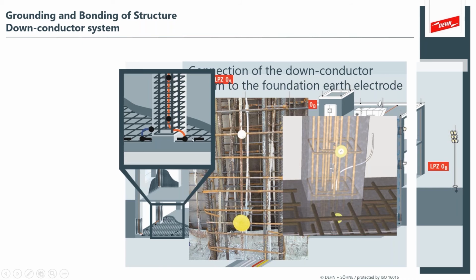So the point of grounding and bonding always comes together hand in hand. And when you have equipment, you might have an electrical control cabinet that might be sitting near this column, and when the structure is complete, you'll have access to that earthing electrode and bonding system with these yellow connection points. And these would be immersed in the concrete and give you a bonding point. That's what's important to remember.